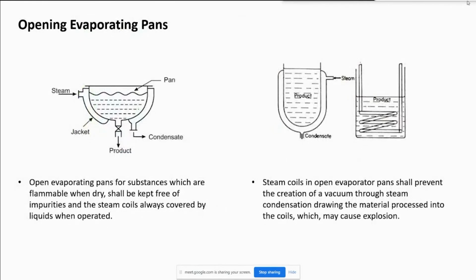Open evaporating pans. Open evaporating pans for substances which are flammable when dry shall be kept free of impurities and steam coils always covered by liquids when operated. Steam coils in open evaporator pans shall be arranged to prevent the creation of a vacuum through steam condensation, drawing the material processed into the coils, which may cause an explosion.